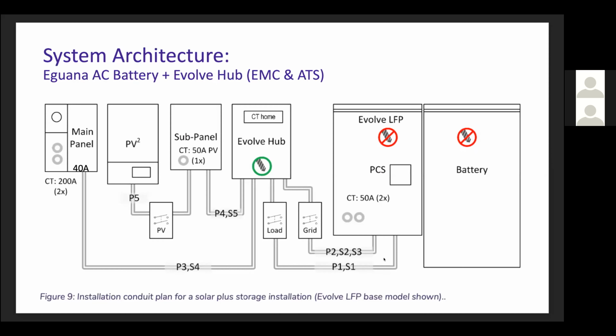Quick look at the system architecture of the Eguana AC battery and the Evolve Hub, which is the EMC and ATS in here, laid out in a simple block diagram. And again, this graphic is from the Hub manual. This is the installation conduit plan for solar plus storage installation. The LFP base model is shown here. The base model meaning that it only has the one battery cabinet and a 14 kWh capacity. If this was a larger system, a 28 kWh, for example, you would just have a second battery cabinet mounted off to the right here.